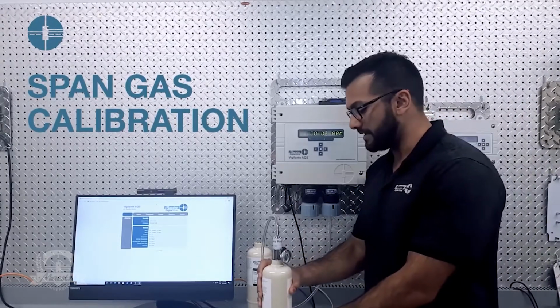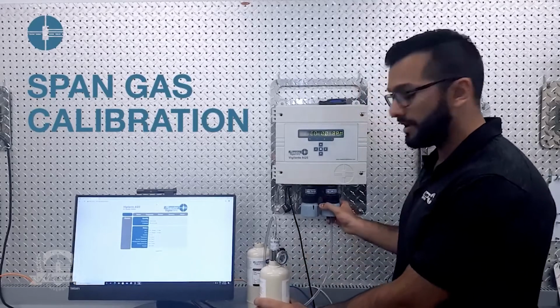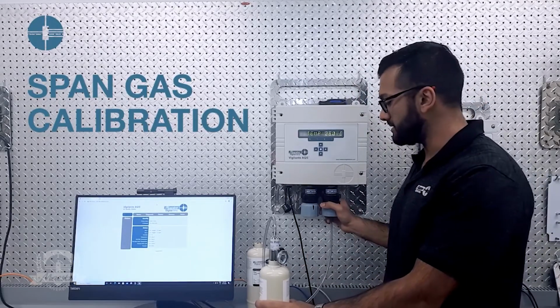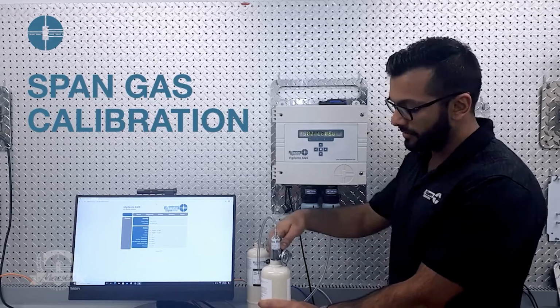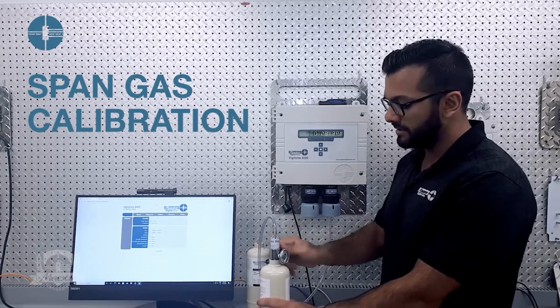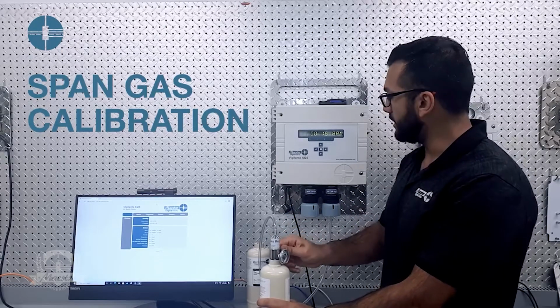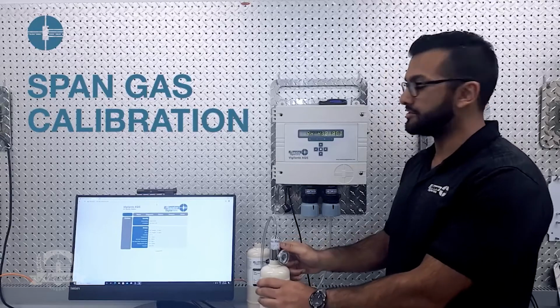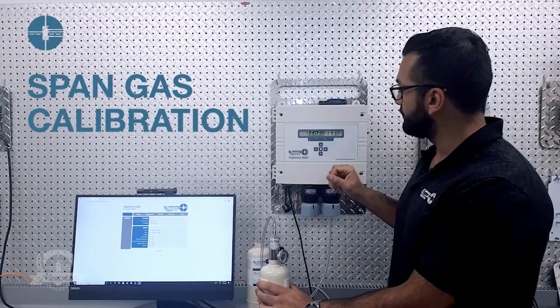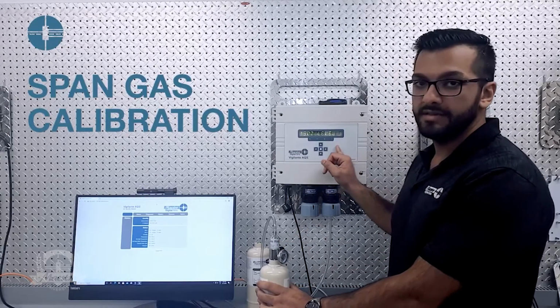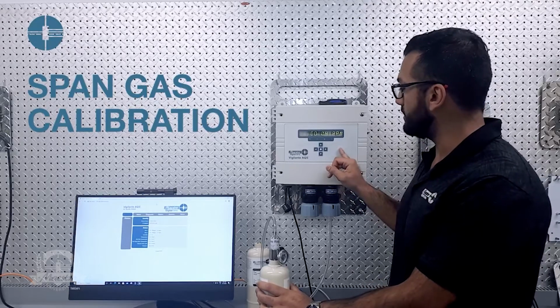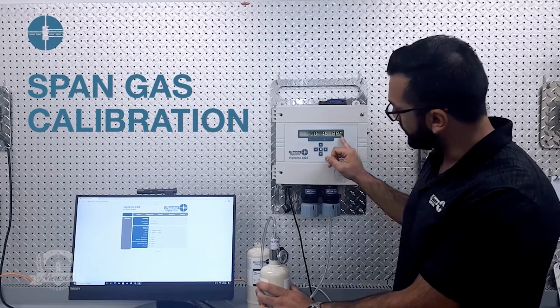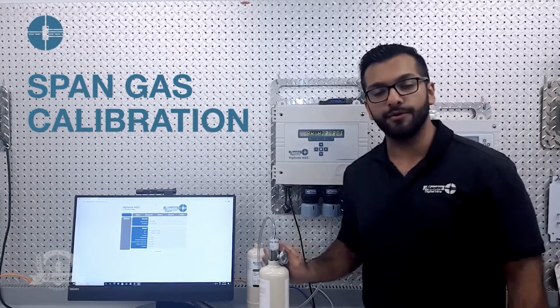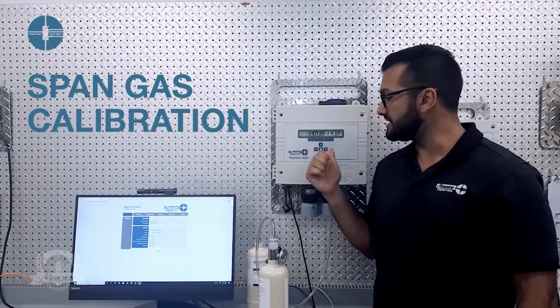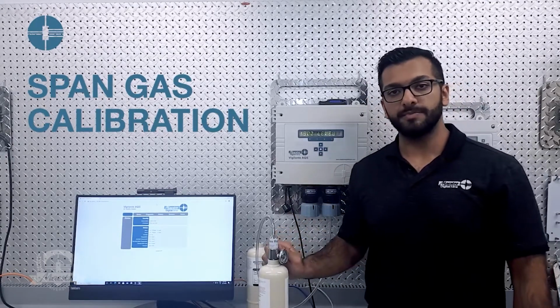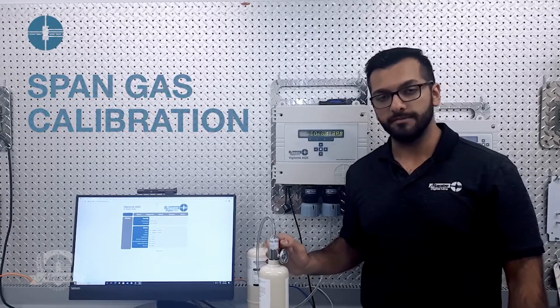Once you've got everything connected, you have to just make sure that your calibration cup is also plugged into the right sensor. You can go ahead and turn the span gas on. And a good indicator to show you that your sensor is actually reading is you'll see on the display the sensor value going up, and as you can see, it's climbing. We're at 1.5. So we'll let that run for 3 minutes, and then we will go through the same calibrate span option right there.